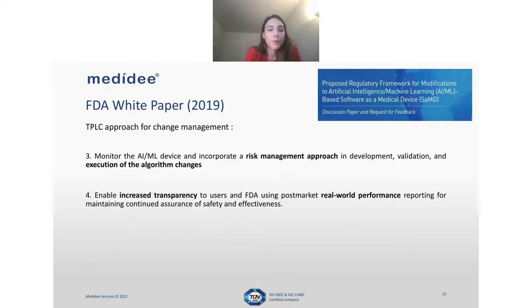Now, the third step is that throughout this process, you need to consider, of course, risk management approaches in development, validation, and during the execution of these algorithm changes. So it's not that you have had the pre-market approval, your device is on the market, and then your risk management stops. To the contrary, because you're implementing changes, it's a lot more important to actually monitor the real world performance. And this is actually point number 4. You are supposed to continuously verify the safety and effectiveness of the device with real world performance data. And you should be able to increase the transparency to users.